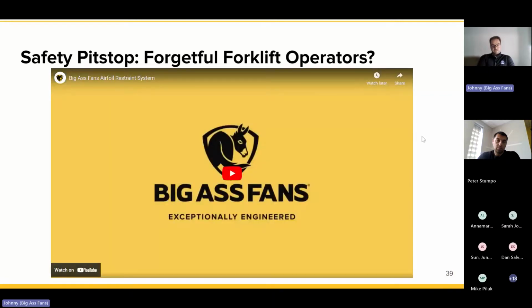We have one more video that highlights a common concern in manufacturing or industrial environments, where a raised forklift comes into contact with the fan. Not an ideal situation, but there are designs implemented to keep the airfoils on the fan—one of them is called an airfoil restraint system. It's good to ask for this: it's essentially a strap, so if the system fails and the mechanical redundancies on the airfoil fail, the strap will hold that airfoil on.